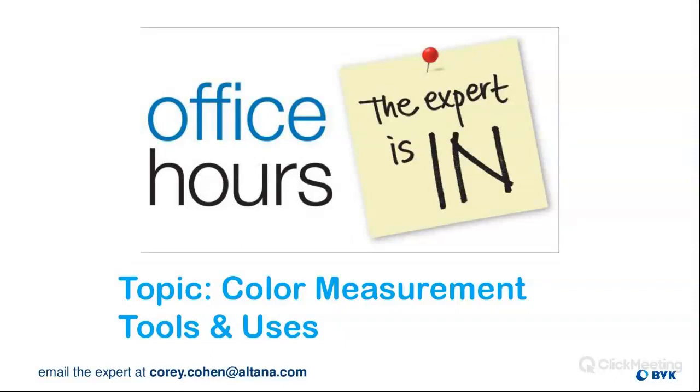How about that? How are these devices calibrated? You want to talk about that calibration, Corey? They're calibrated on a white tile, and then you can check the calibration. They each come with a green checking standard, and there's a function in the instrument itself where you can do a check green test, and it will measure it and tell you whether it's in calibration based on the values programmed into the instrument.